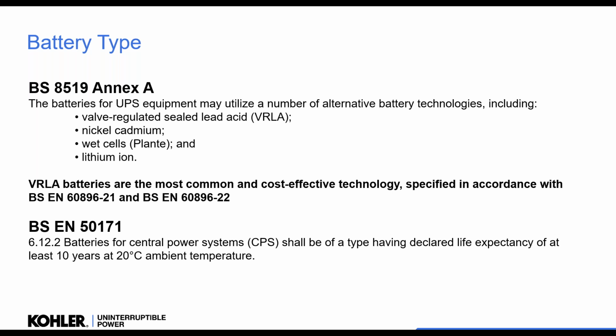Now, 50171, like I said, has some other important information, because it talks about, as guidance, that central power systems should use a battery that has a declared life expectancy of 10 years at 20 degrees. A lot of the other regulations don't talk about this life expectancy. There's a lot of UPS batteries that are 3 to 5 year batteries. It's not really cost effective, and you're replacing them often. So having a 10-year plus battery is actually the right thing to do.